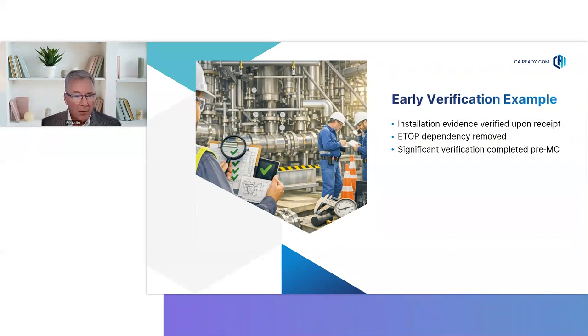To make this more concrete, consider a stick-built WFI storage and distribution loop, which is a verification-intensive system on many projects. One simple example of the broader opportunity is vendor-supplied calibration certificates. Instruments for a WFI loop typically arrive with calibration already performed by the manufacturer. These certificates are reviewed for range, accuracy, traceability, and suitability, but on many projects, that review is deferred until mechanical completion simply because it's bundled into a final turnover package.